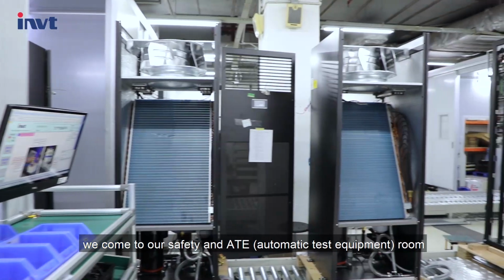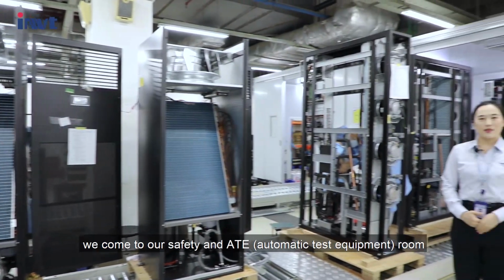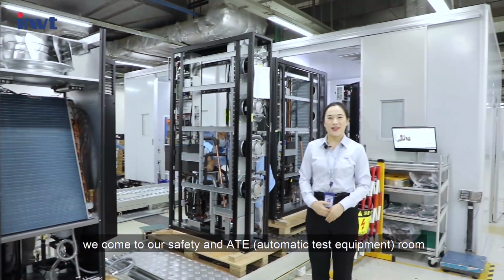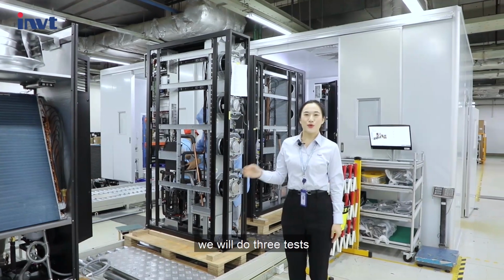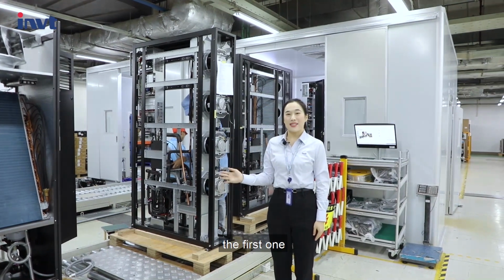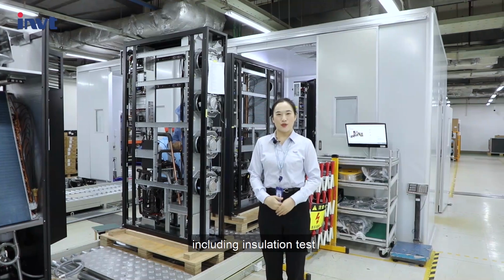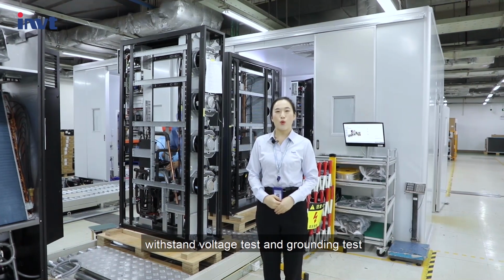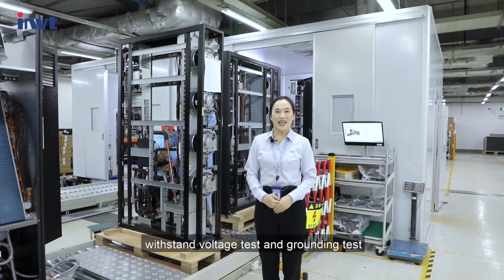Now we came to our safety and ATE, automatic test equipment room. In this room, we do 3 tests. The first one is safety testing, including insulation test, withstand voltage test and grounding test.